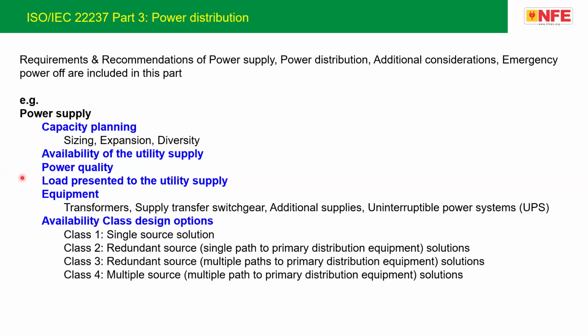So these are the systems, and next, if I talk about the UPS, the UPS should be designed with respect to normal operation when we are feeding from the UPS, and when the UPS is running in bypass mode and the power is fed from the utility. So that has to be taken care of.